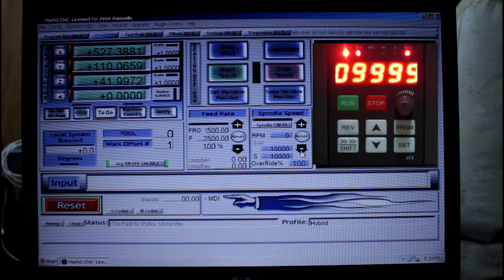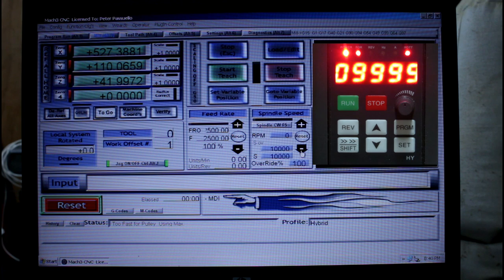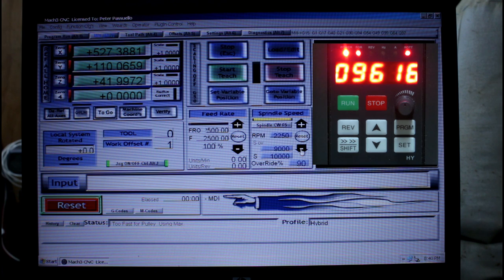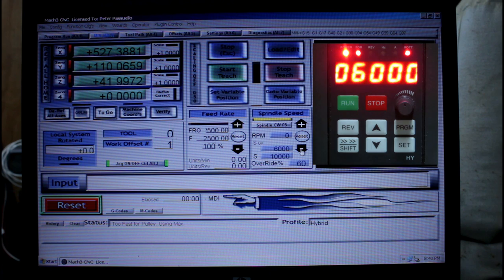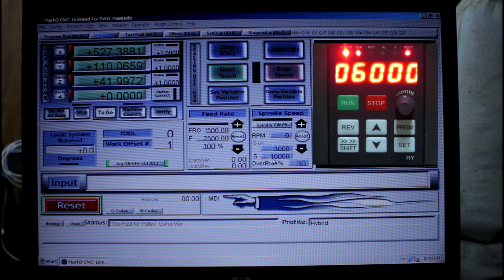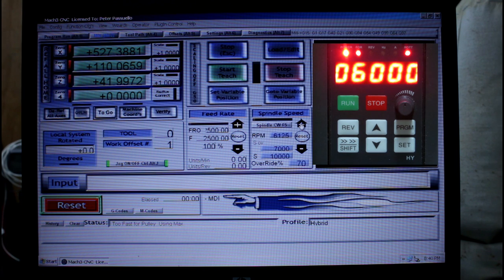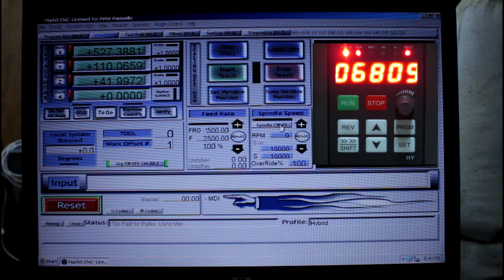Until we finally reach maximum speed. I'll just hit the reset button and it'll come back to our 10,000 level. Now you'll actually notice that 10,000 RPM actually shows us 9,999 RPM on the actual VFD itself. I think we can live with one RPM difference and we can go down as far as 6,000 RPM. If I go any lower it shows a lower figure here but the VFD's programmed not to go below that figure. And again I can come back up again, it works a treat.